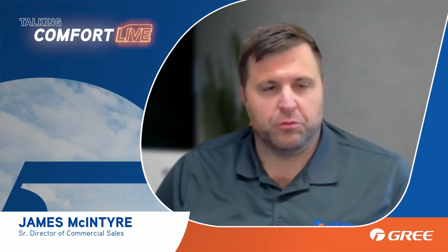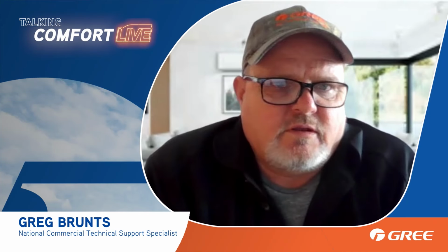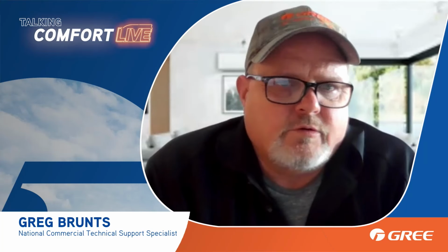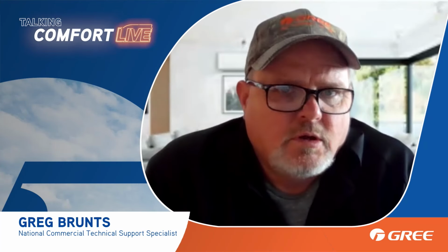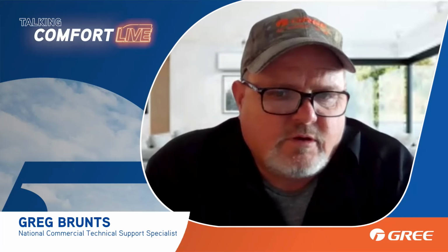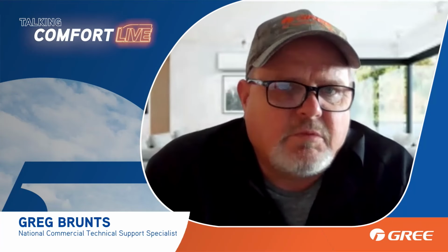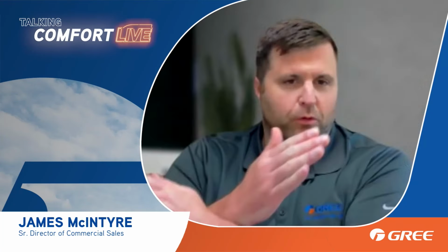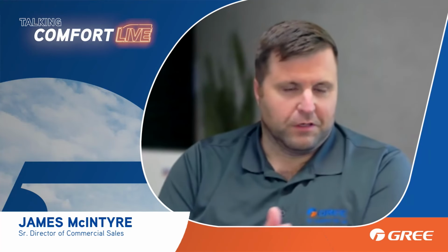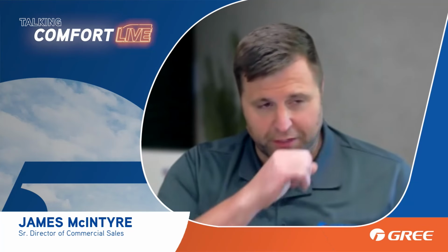There was always an argument over whether setback while the space was unoccupied was a savings. Well, in cooling mode, it's never been a savings, unless you're doing like a degree or two. If you're putting huge temperature differences, no, you're definitely not saving money - there's going to be some kind of crossover point. If you're having to catch up 10 degrees, it's going to take a significant amount of run time to make up for that, and at some point it would have been cheaper just to maintain.